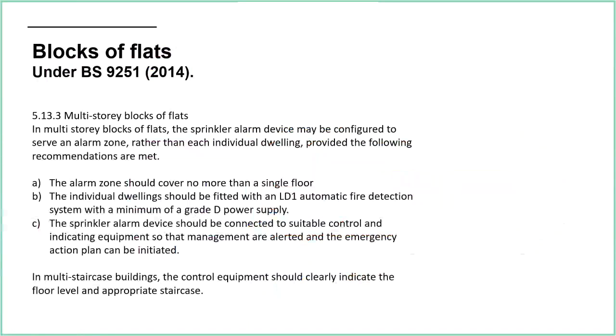So let's have a quick look at what it says. This is it, by the way, under 9251, the current version, which is 2014. As we keep mentioning, there is a new one coming out soon. But for the moment, this is it in terms of multi-storey blocks of flats. So it says here that where you've got these multi-storey blocks of flats, the sprinkler alarm device may be configured to serve an alarm zone rather than each dwelling, provided the following conditions are met.